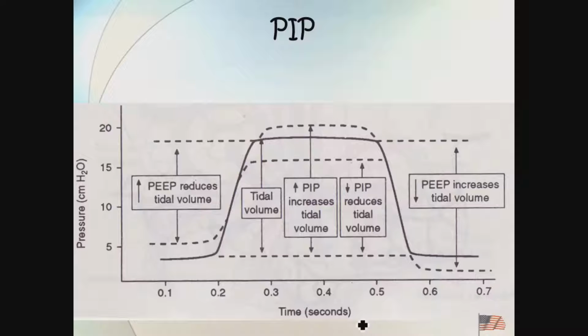Okay. Unlike pressure ventilation in the adult world, which is always referenced to the baseline pressure, this is different. These are two separate pressures. And this concept will come back to us in the summer. Okay. What determines tidal volume? The difference between the peak pressure and the baseline pressure. What I'm going to call delta. That's the difference between the peak and the baseline, called delta. Not delta delta. That's all it's saying. Delta determines tidal volume. The change in pressure.